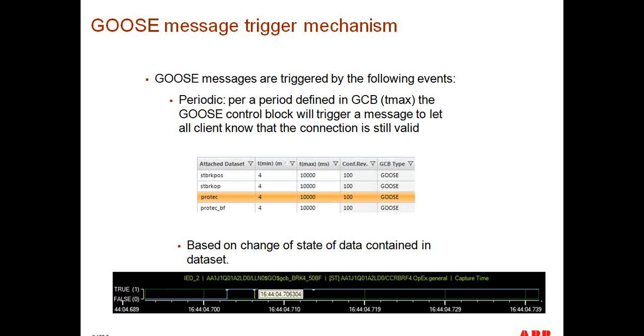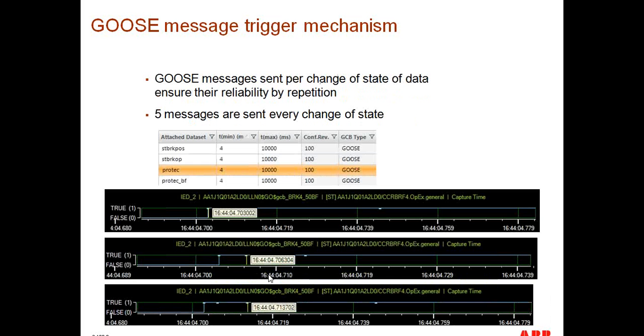The second delivery mechanism, which is more interesting, is based on the change of state of the data. In this particular case, we can see how the information contained in this Goose message, which is for breaker fail, the operation of a breaker fail element, changed from 0 to 1 at this particular time. So whenever it changed state, we send a Goose message.